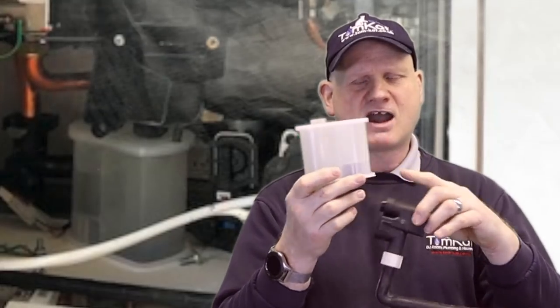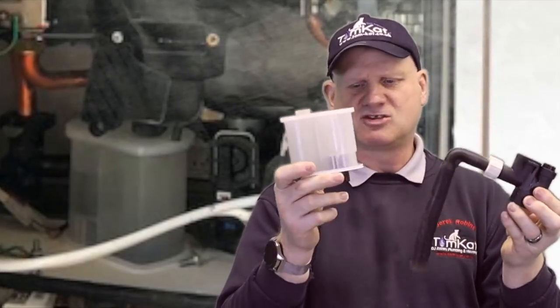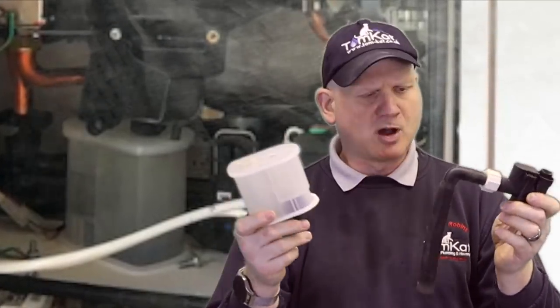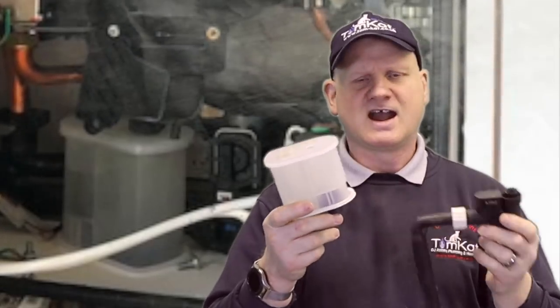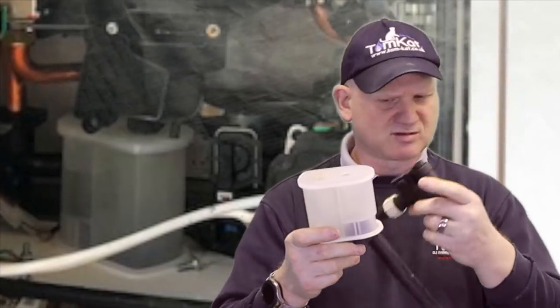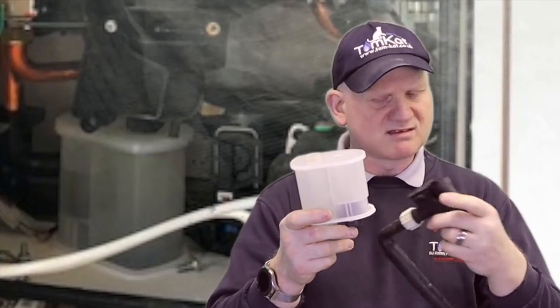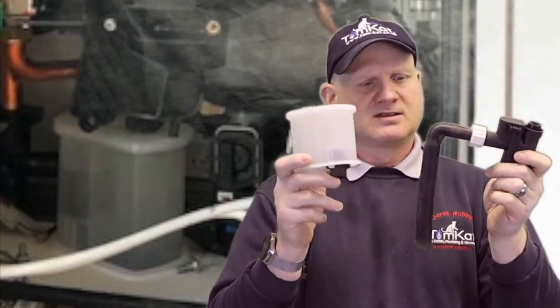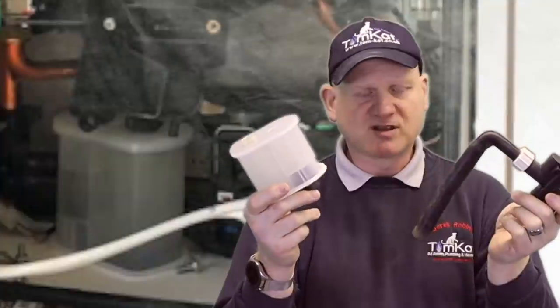And these now have to have a 75 millimetre trap in there to help with getting rid of the condensate and to stop smells and products of waste getting back into the boiler. So that's how traps have evolved.